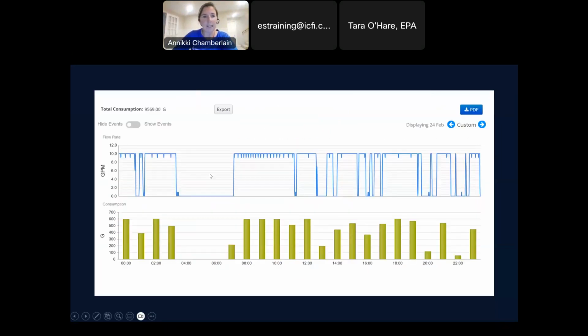So look in the 1-minute data. Again, this is a blowdown. The top one is my signature, my heartbeat basically, and the bottom one is the gallons. So this tells me my blowdown is working. It's not stuck open, right? It's coming on and off. Here my blowdown is running, then it turns off, then it's on, then it turns off. So it's not a mechanical issue with my blowdown valve, but something is telling the tower to blow down all the time. These are incredibly long blowdown times.